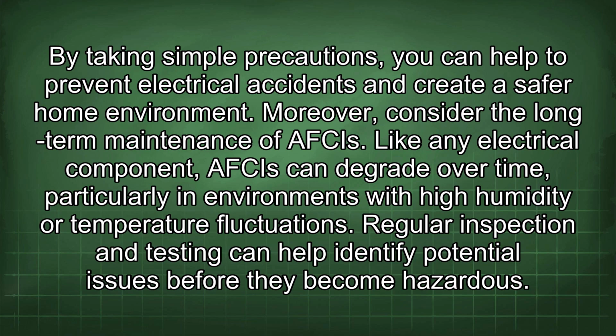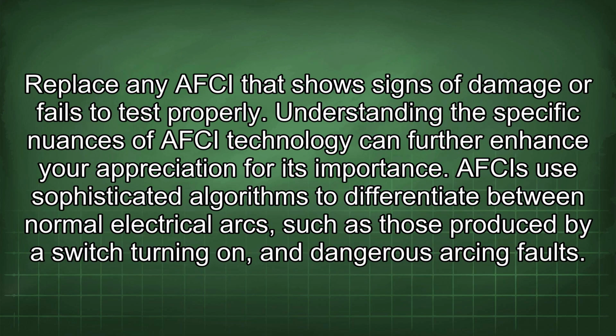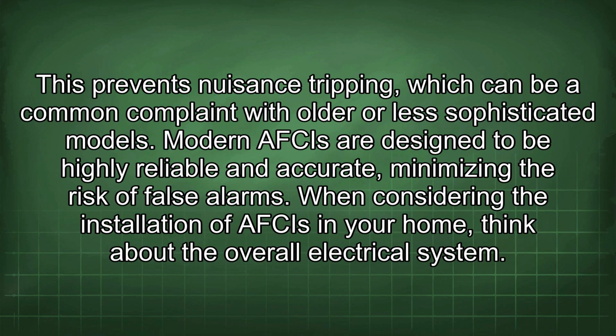Moreover, consider the long-term maintenance of AFCIs. Like any electrical component, AFCIs can degrade over time, particularly in environments with high humidity or temperature fluctuations. Regular inspection and testing can help identify potential issues before they become hazardous. Replace any AFCI that shows signs of damage or fails to test properly. Understanding the specific nuances of AFCI technology can further enhance your appreciation for its importance. AFCIs use sophisticated algorithms to differentiate between normal electrical arcs, such as those produced by a switch turning on, and dangerous arcing faults. This prevents nuisance tripping, which can be a common complaint with older or less sophisticated models. Modern AFCIs are designed to be highly reliable and accurate, minimizing the risk of false alarms.